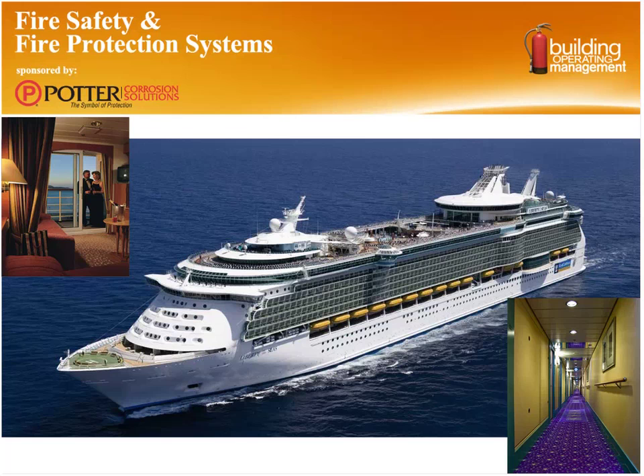Now, why does the cruise industry want to use fine water mist? Well, it really boils down to revenue protection. If you think about it, that ship needs to be able to turn and go back on the next cruise in 7 days, 14 days. Fires happen. I mean, we've seen them. Fires happen on ships. If they were to happen in one of the guest rooms, potentially that guest room and any associated guest rooms, or maybe even that whole floor or the next floor below, could put that ship or a good block of that ship out of commission while they refurbish that space.